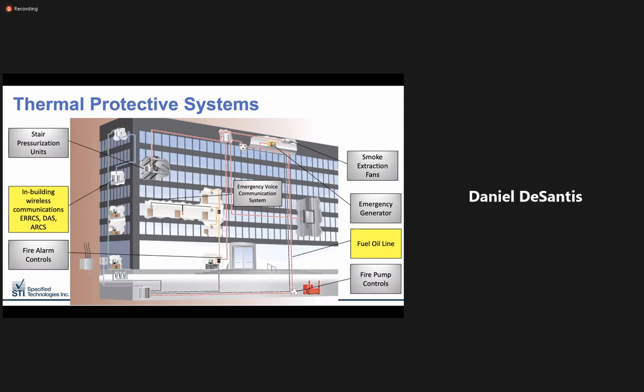This graphic gives us good perspective on how thermally protective enclosures are utilized in modern construction. All of these services, from fire alarm cables to smoke extraction fans, utilize passive fire protection in order for their circuitry to remain operational under the extreme temperatures of a building fire. We'll be focusing closely on in-building wireless communication as well as mechanical fuel oil piping. But as you can see, there are many use cases for passive fire protection. Most are related to electrical circuitry.